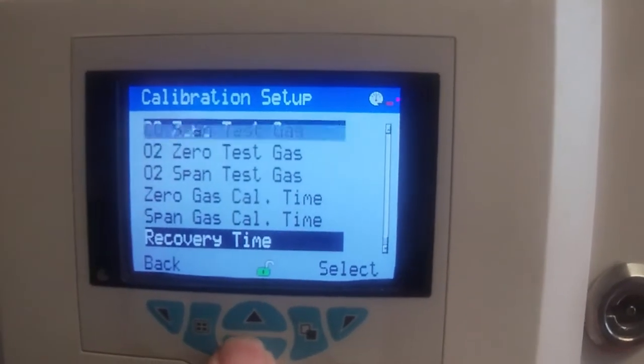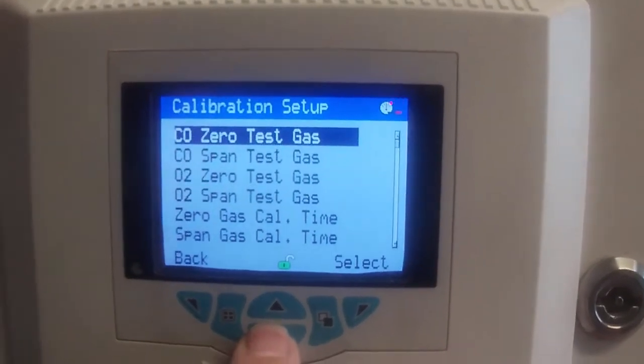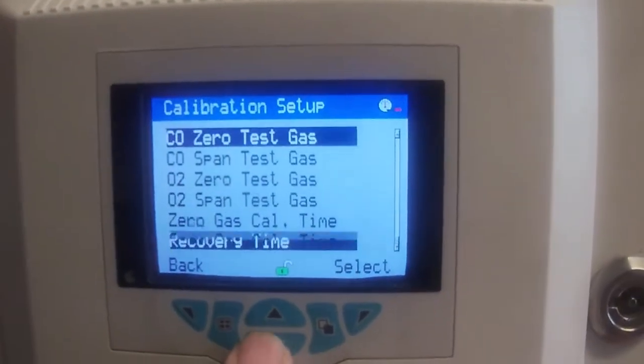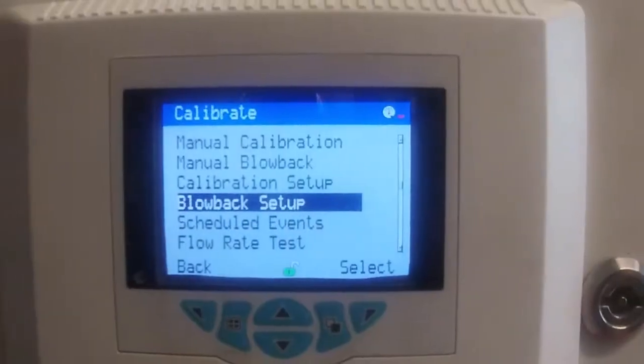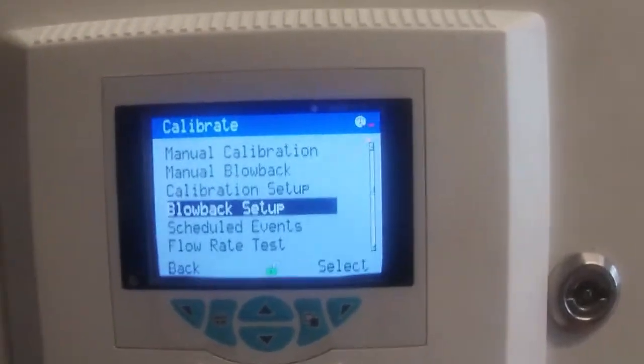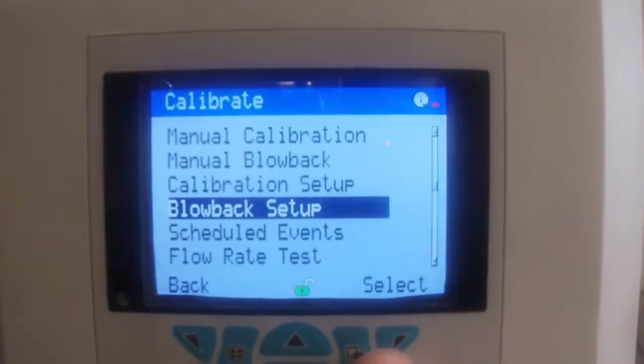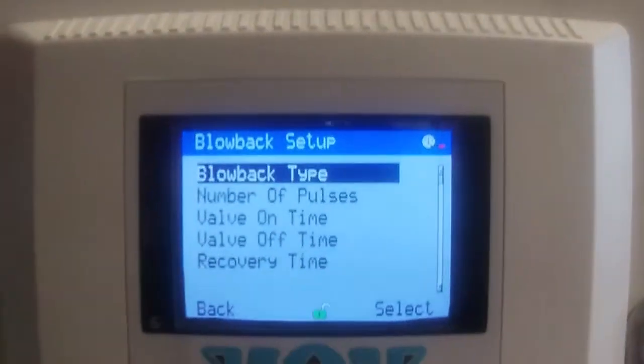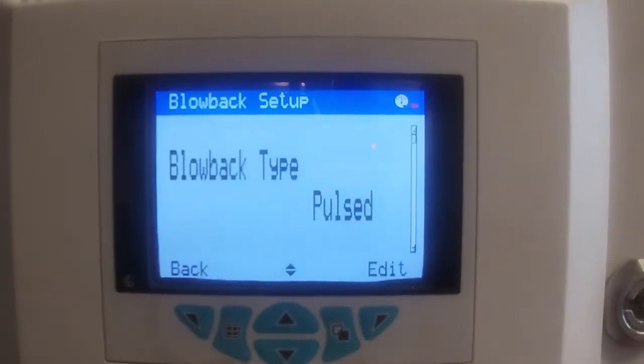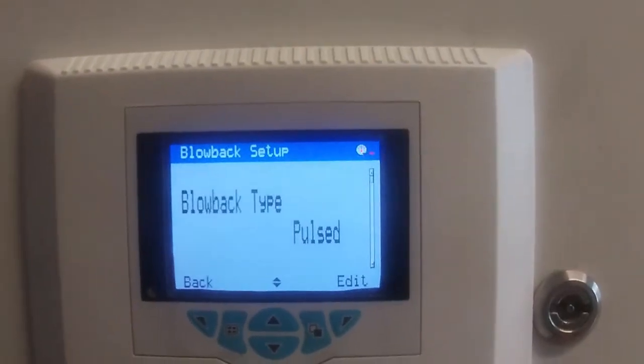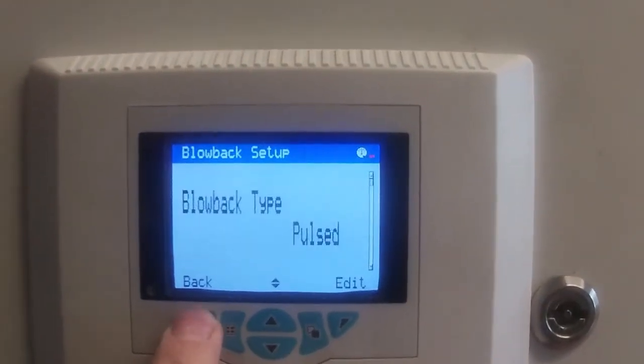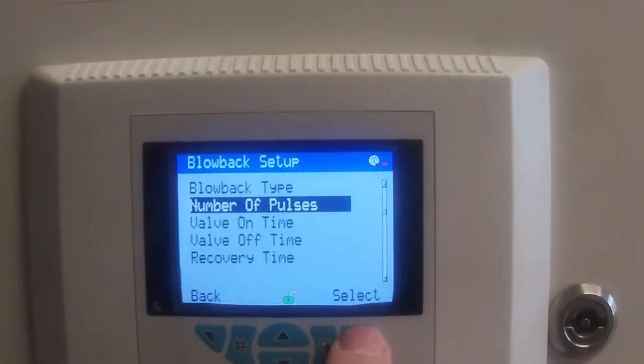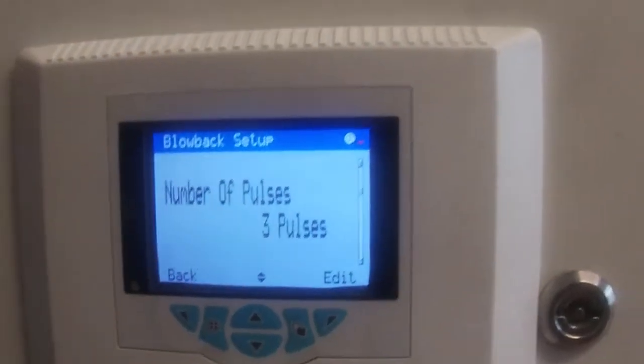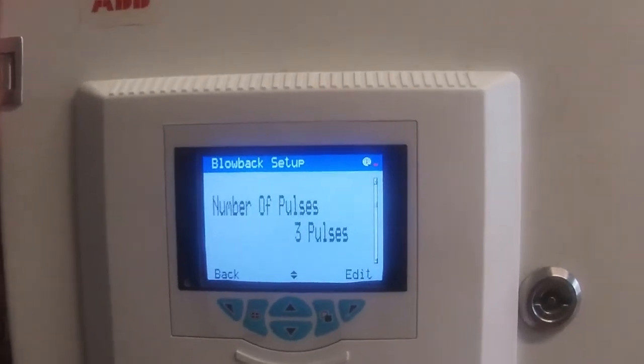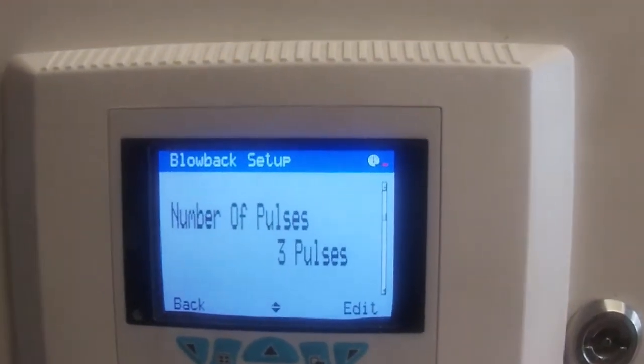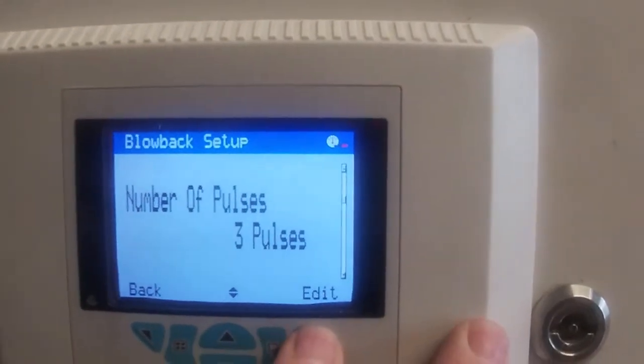Back. I think we are at the end of this one. Yes. So the next one is blowback setup. You can actually have this thing automatically blow back. So what type of blowback do you want? Well, basically a pulse. You want to give it a pulse of air. It's not on all the time. And then the number of pulses. I think I set that for 3. So pulse, and then a pulse, and then another pulse. And later when we do the calibration, you'll actually see it do that.